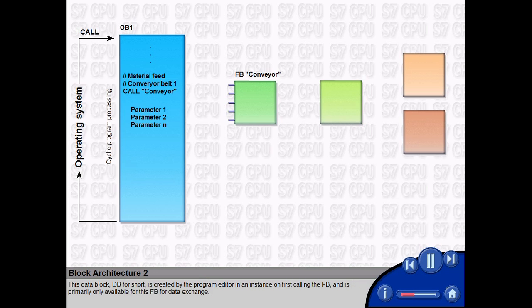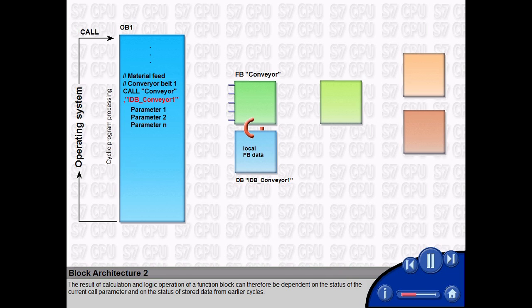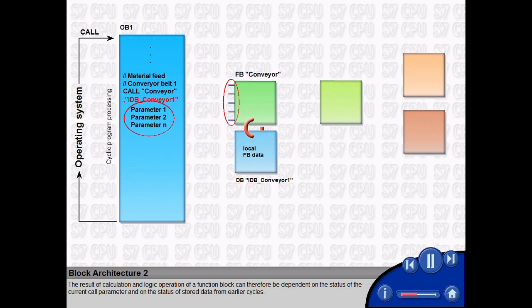This data block, DB for short, is created by the program editor in an instance on first calling the FB and is primarily only available for this FB for data exchange. The result of calculation and logic operation of a function block can therefore be dependent on the status of the current call parameter and on the status of stored data from earlier cycles.